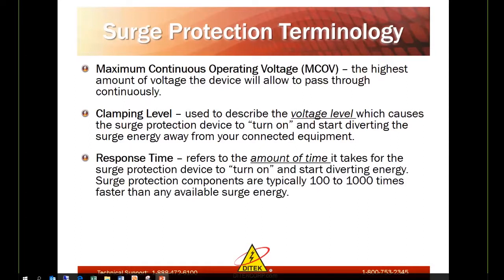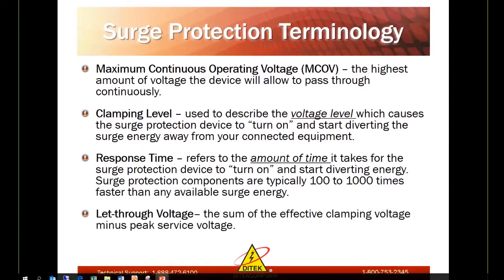Response time is the amount of time it takes for our surge protection device to turn on or react and to start diverting the energy or dissipating the energy to ground. Surge protection components are typically 100 to 1,000 times faster than any available surge energy entering your facility. Let-through voltage is the sum of the effective clamping voltage minus the volt peak service voltage.